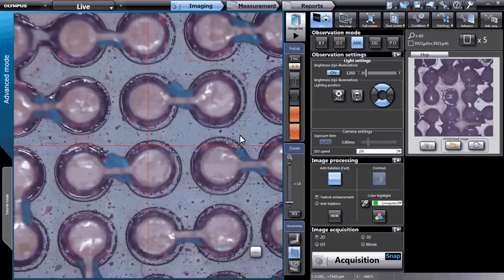Advanced acquisition functionality is available on the DSX series Opto-Digital Microscopes that are equipped with a motorized stage. This function will allow the user to define an origin point on a sample, then provide two points to deskew or correct for any rotation of the part on the stage. Once this is accomplished, a set list of inspection points can be loaded, and the system can be programmed to visit these points and perform a predefined image acquisition.